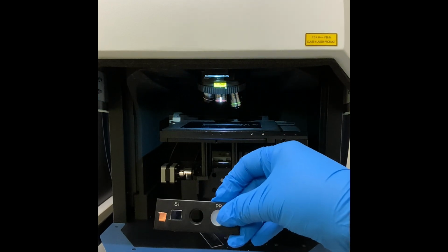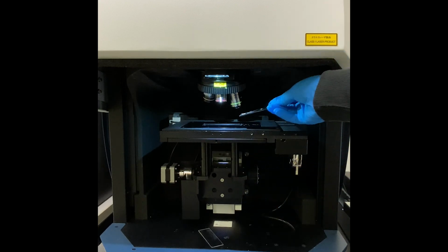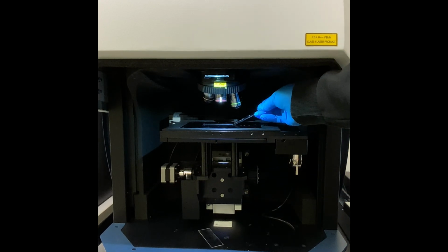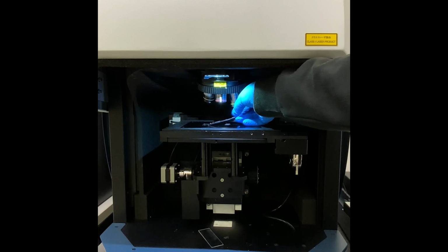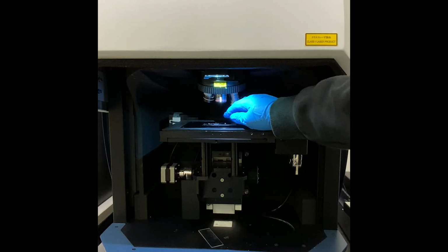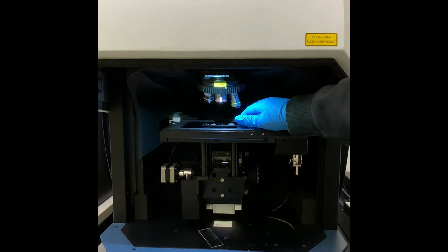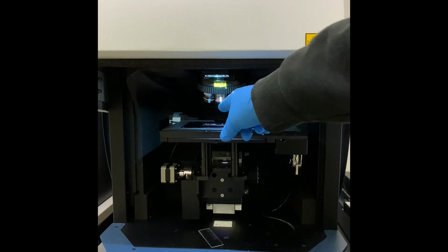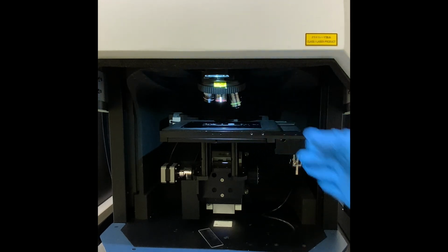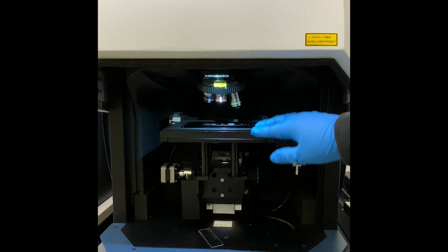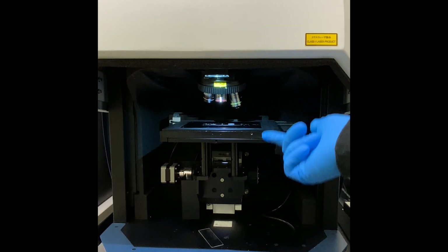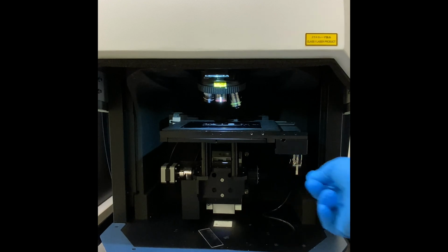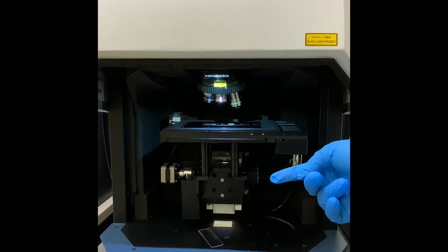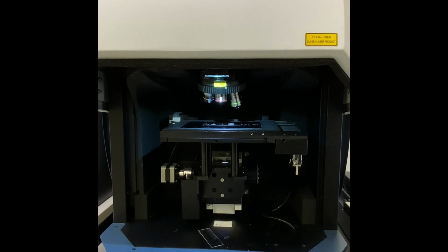So I'm going to put my sample into the sample holder at the top here, and I'm just going to slide it in. And there is a metal prong to the left of it that you slide the sample against. So again, this is the stage for the sample. The stage moves up and down, which is Z, left to right, back and front, which is X and Y. And that can be controlled using the software or using the joystick.